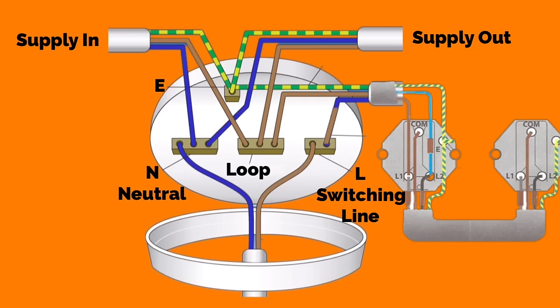It doesn't matter if your L1 and L2 in the first switch are in L2 and L1 the opposite way around in the other, as long as the common cable remains the same. So if you've chosen to use brown common in the three-core cable, it must be positioned in the common terminal of the second two-way switch in order for it to function correctly.